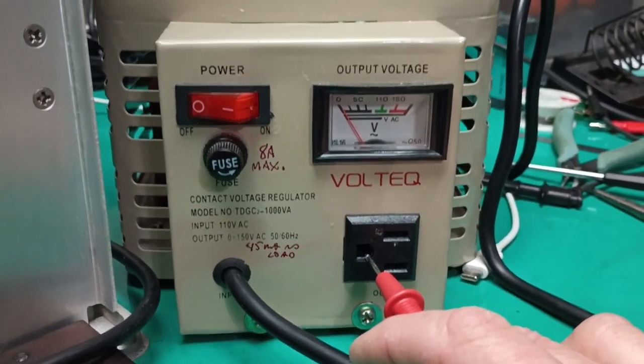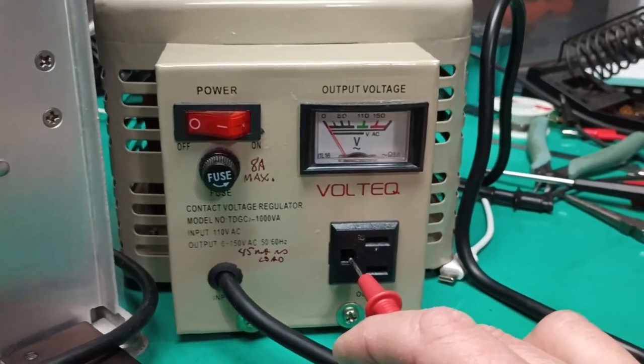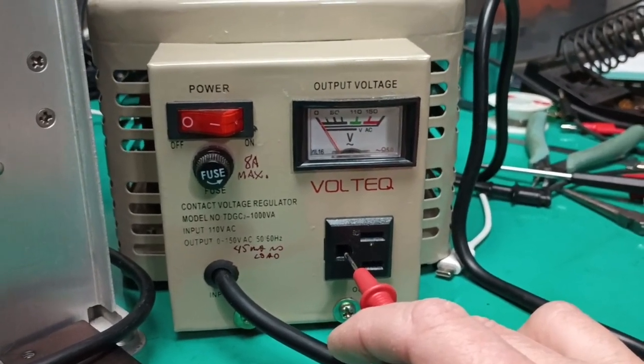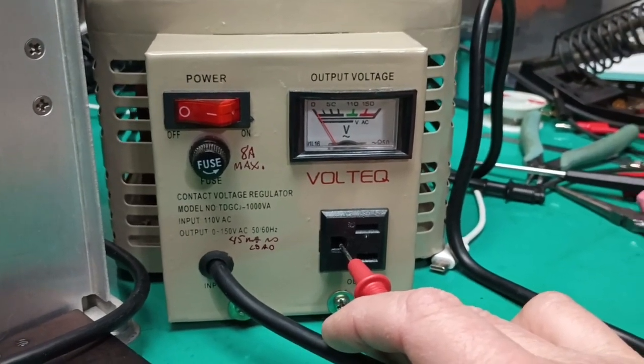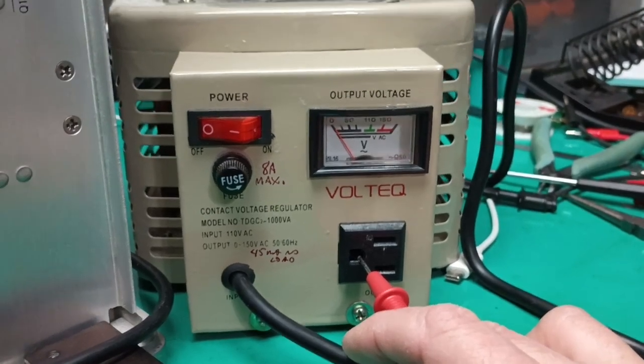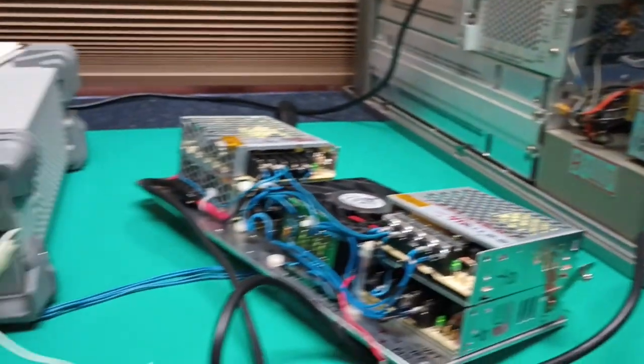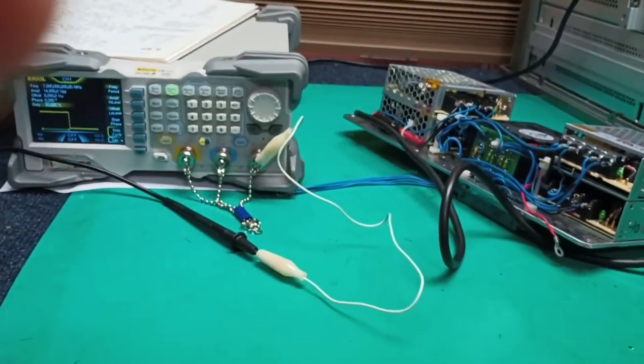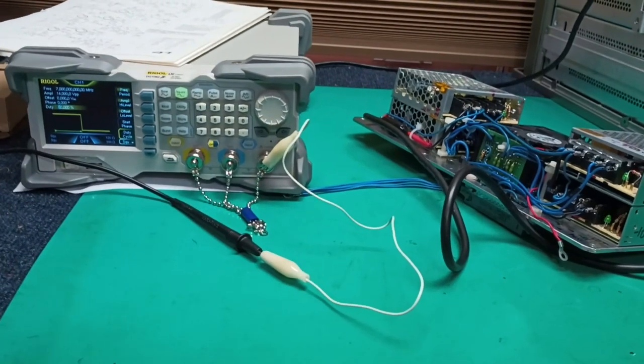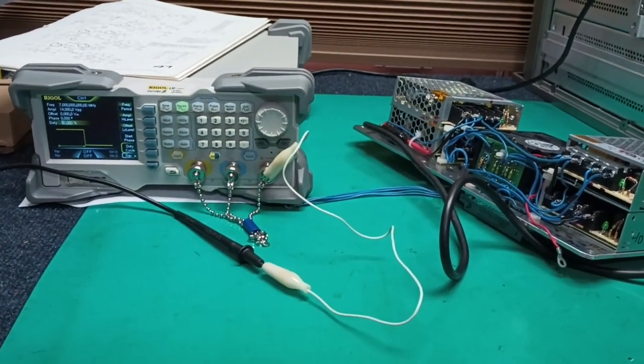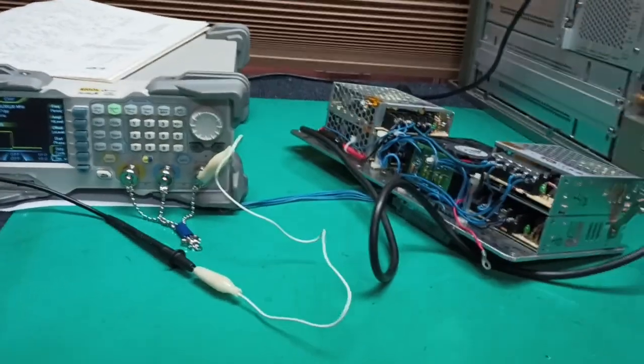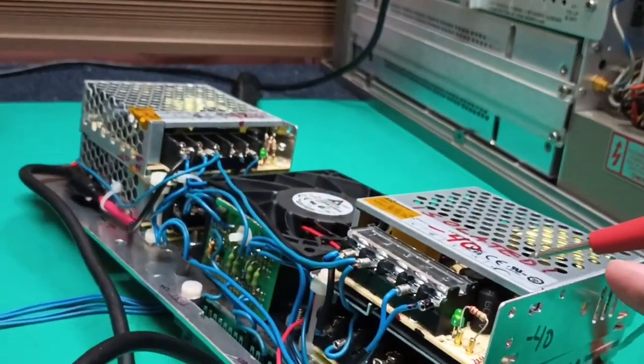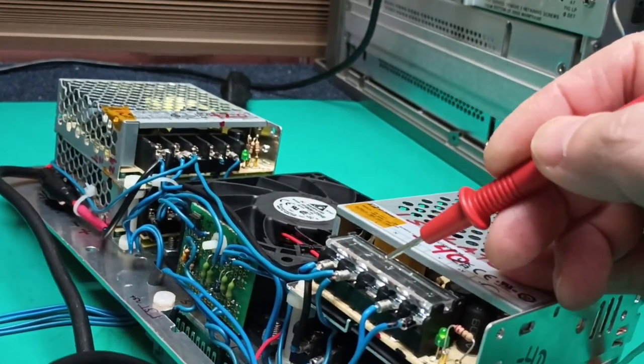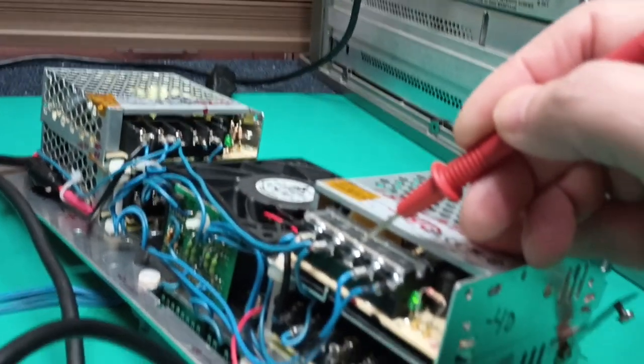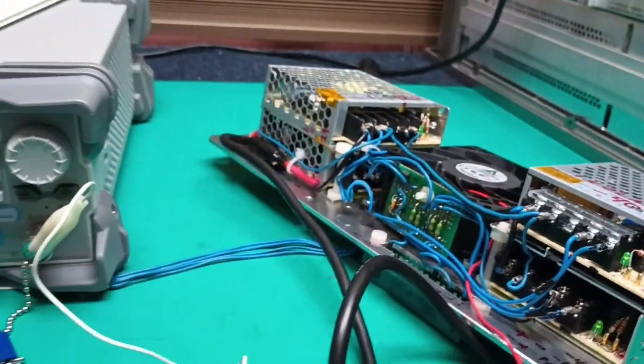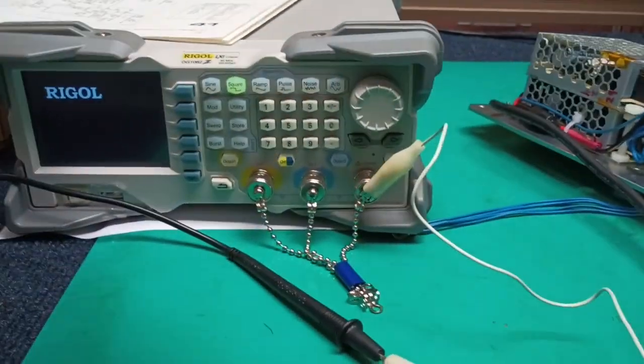grounded out, now that's causing a current that's going down one leg of that 150 foot of cable and coming back the other 150 feet. We've made a big ground loop. Now, as far as AC line current goes, who really cares? It's not a crisis. The problem is that makes a huge RF pickup. So now there's a big loop antenna between these two terminals, and they're coupled to these. And this is where strange RFI problems come from.